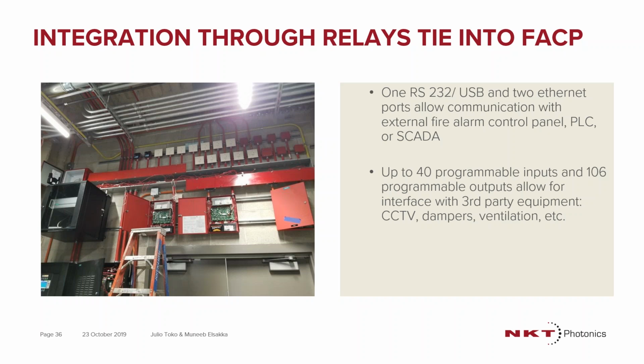One advantage, being for tunnels, is that we've been integrated to CCTV. So if we do a pre-alarm per that zone, the CCTV camera in that zone can be activated to zoom in and look at the area. We can use dampers to be able to block areas, such as activation of a damper. Ventilation, we can activate the ventilation system, whether it's in a tunnel where there is a lot of cable trays or a tunnel in different areas, for instance, subway tunnels. This ventilation system can be activated by our system.